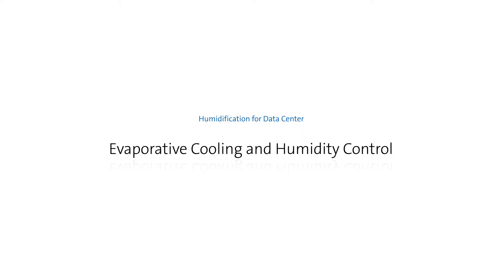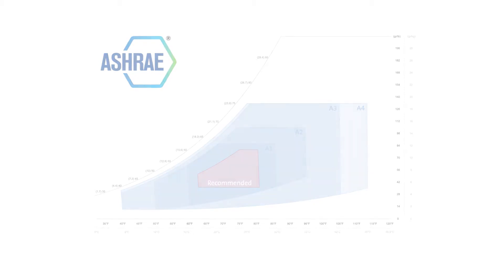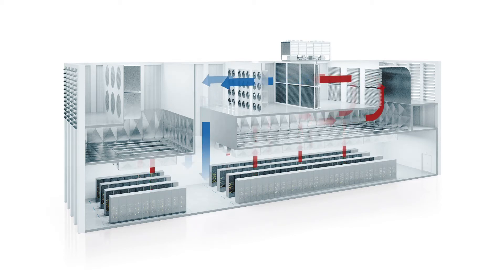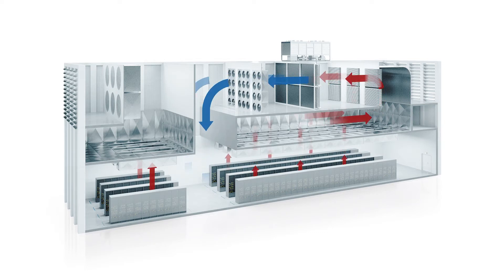Evaporative cooling and humidity control for data centers. Since ASHRAE expanded its guidelines on air conditions for data centers, cooling strategies have mostly focused on using large volumes of outdoor air to cool data halls, rather than compressor-driven chillers. This trend has led to much lower power usage effectiveness for the industry, and many newly constructed hyperscale data centers being located in colder climates to take advantage of this economic cooling technique.